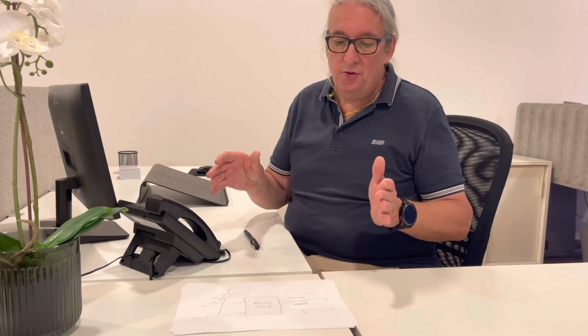It should be fed through an RCD. Now, I know in some countries they don't use RCDs, they don't exist, but generally they should be used. Use an RCD in conjunction with an MCB, main circuit breaker. A circuit breaker is different. A circuit breaker is for overload. The RCD or the ELCB is for earth fault.